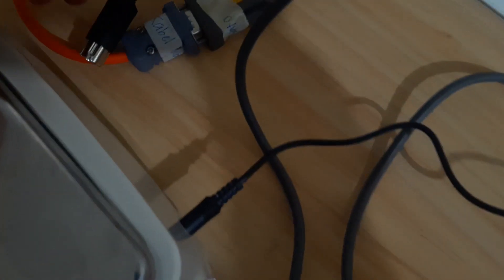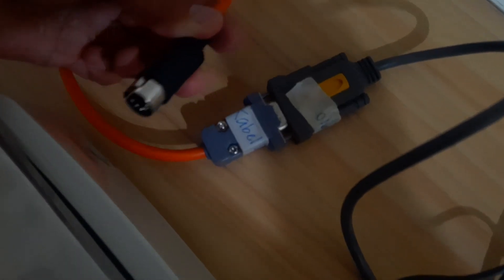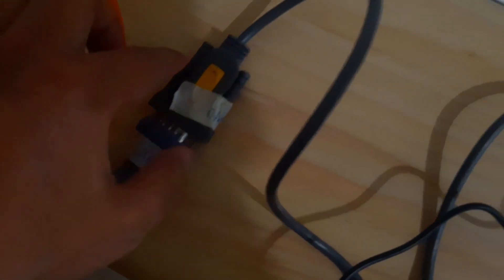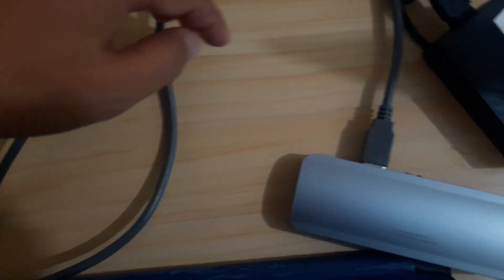This analytical balance has an RS232 output with five pins for communication, both for retrieving weight readings and sending commands. From the RS232, I'm using an RS232 to USB converter to connect it to the computer.